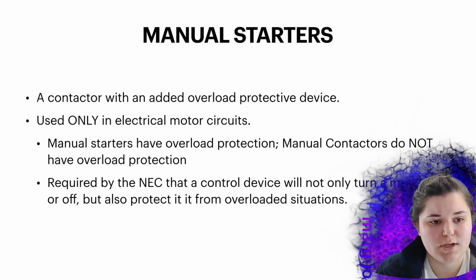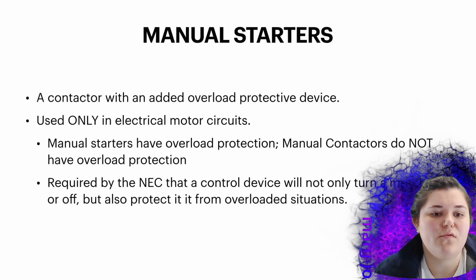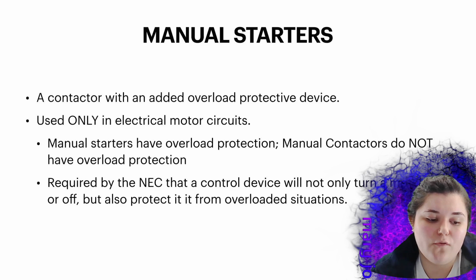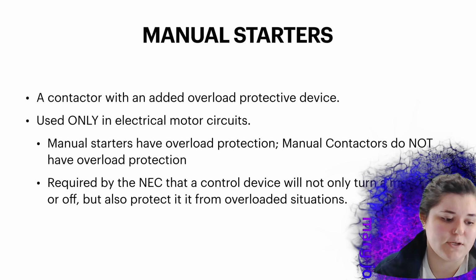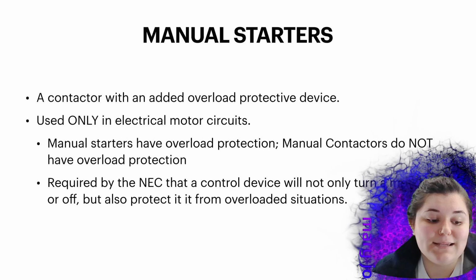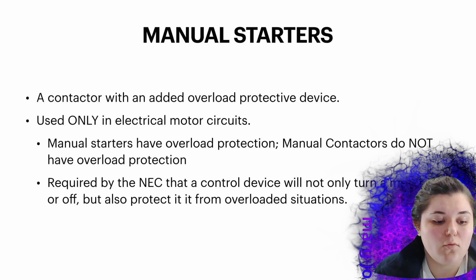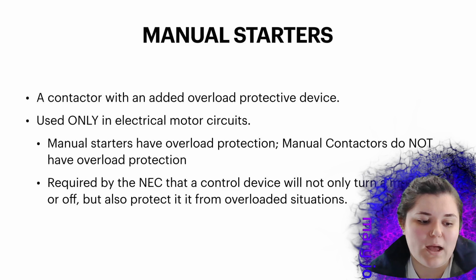Manual starters. A contactor with an added overload protective device used only in electrical motor circuits. Manual starters have overload protection. Manual contactors do not have overload protection. It's required by the NEC that a control device will not only turn a motor on or off, but also protect it from overloaded situations. That's why it has overload protection.